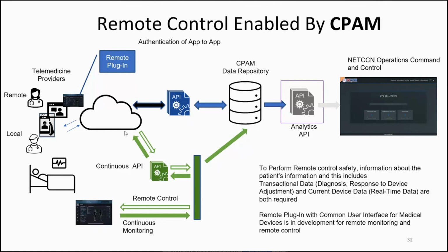There are multiple pieces of this we're looking at. One is the ability to provide a plugin from CPAM for the telemedicine providers to remotely control and review this data, but also just giving the ability to remotely control ventilators and infusion pumps from a distance as part of this ongoing infrastructure. This would also enable alarms and other decision support applications to run across this real-time infrastructure and have better communication between the bedside and that remote provider.